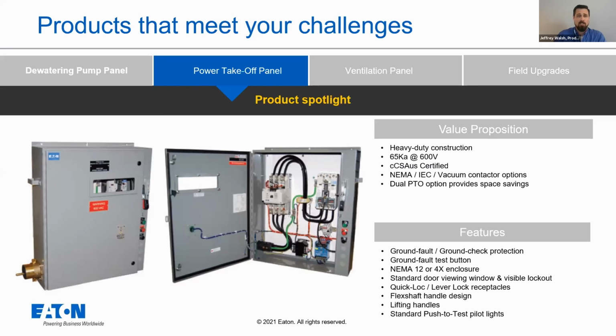We have a single PTO offering which has one contactor and is used to switch the power to just one load, but we also offer a dual mode as well. The typical dual comes with two contactors, but can only have one operating at a single time. And that's selected at the door of the enclosure by the operator via a selector switch. But we also have a dual concurrent model, which offers the user the ability to have both contactors energized.